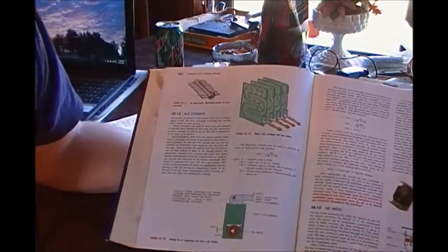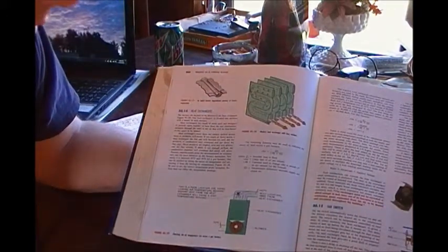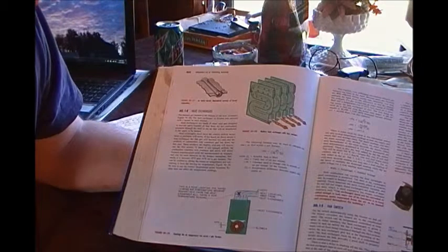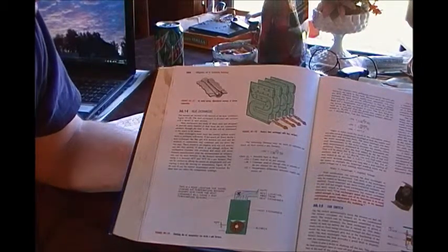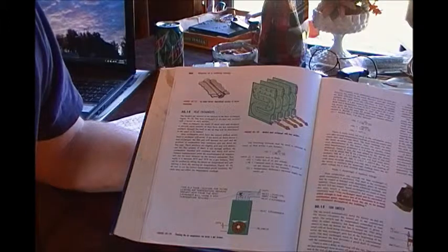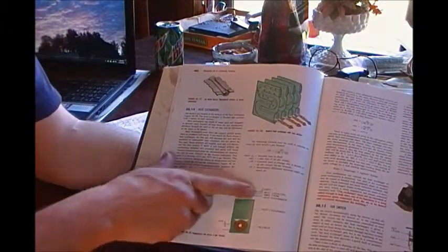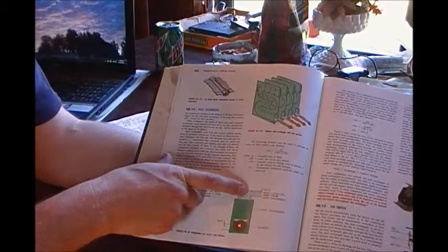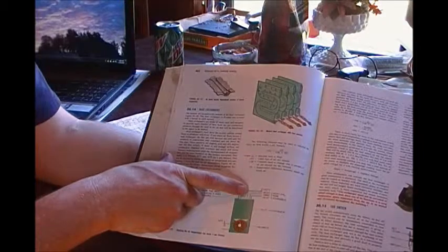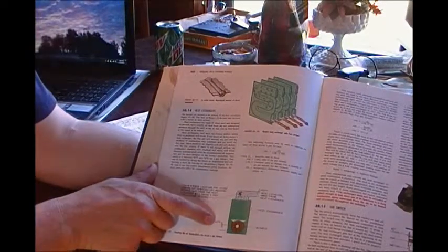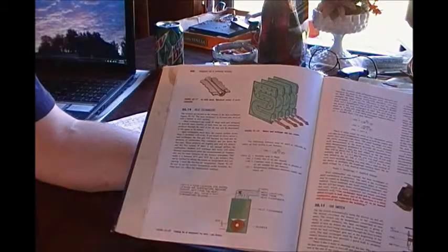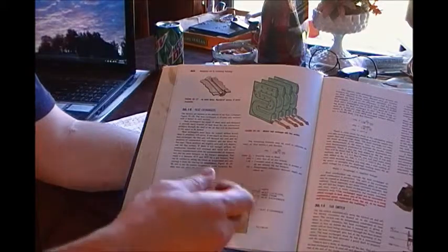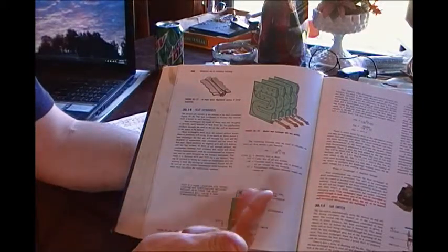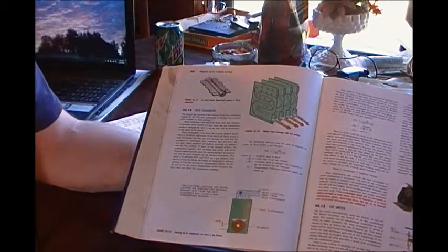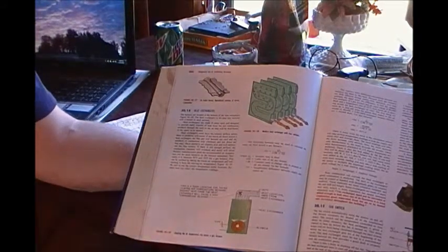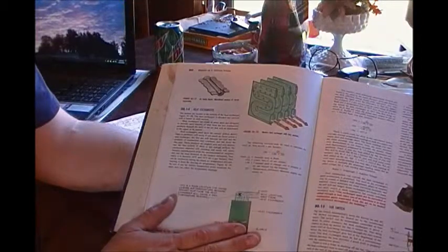And say you're getting 170 out of that thing. You've got 70 going in and you're pumping out 170. Well, that's way too much. Because pumping in 70 and pumping out 130, anybody can figure it out with your fingers if you have to: 70, 80, 90, 100, 110, 120, 130. That's 60 degrees difference. We're running within our 40 to 70 degree difference.